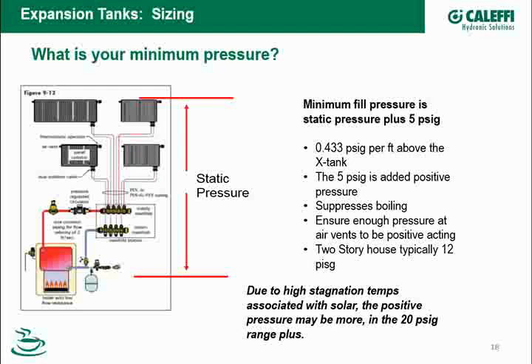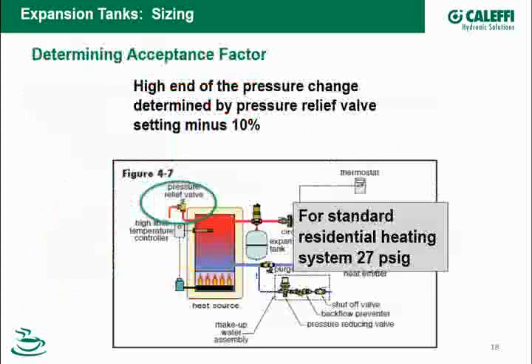Next, I need a maximum pressure. The maximum pressure is based on keeping the relief valve from lifting. So in a typical residential application, I have a 30-pound relief valve. Now, I don't want to push that pressure all the way up to 30 pounds. Most relief valves tend to start leaking before they get to the actual fully open pressure. That happens usually at about 5% away from the design pressure. To keep the relief valve seated, most people will design 10% less.